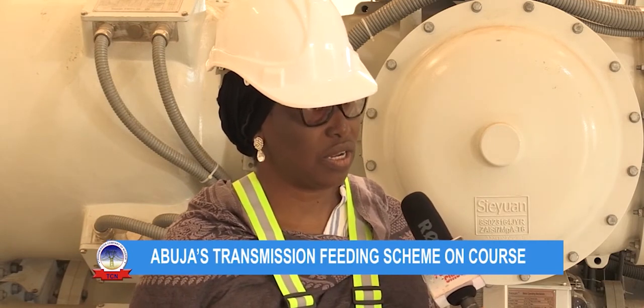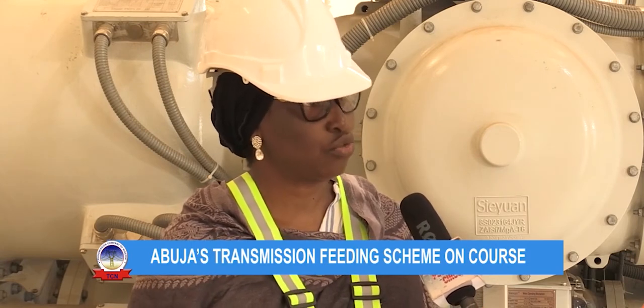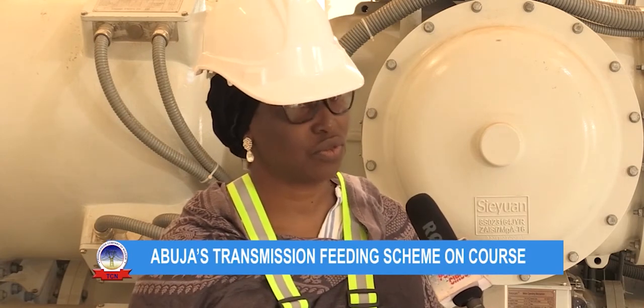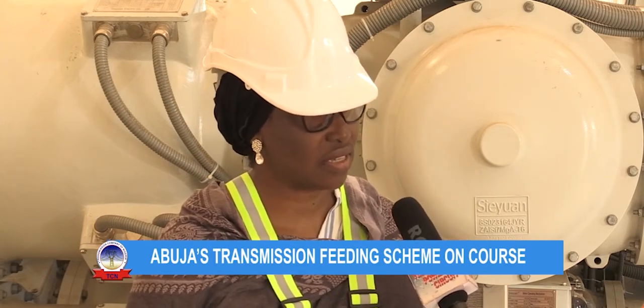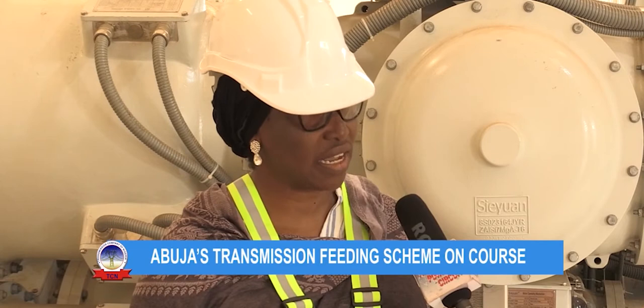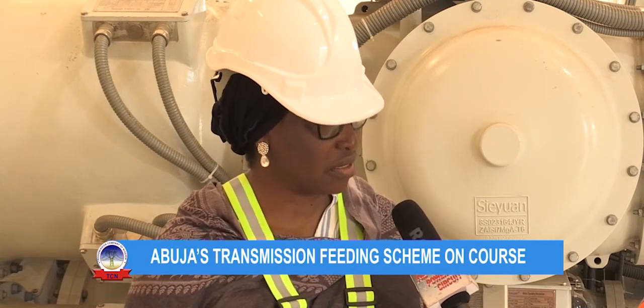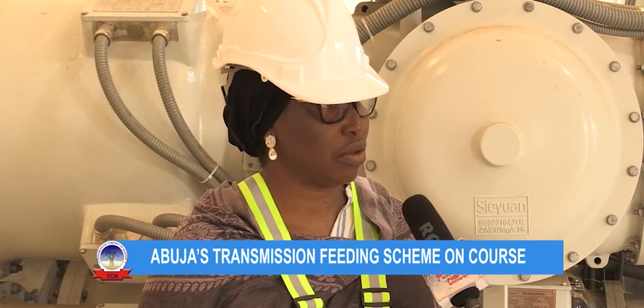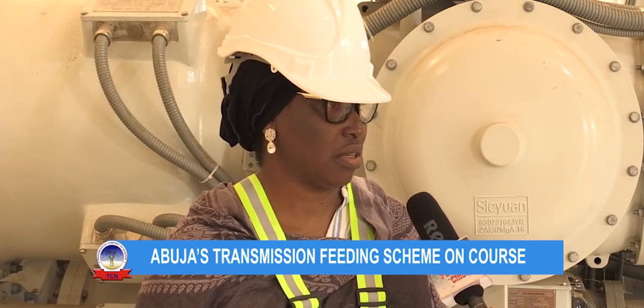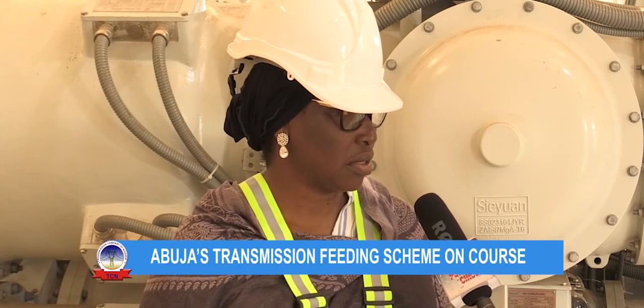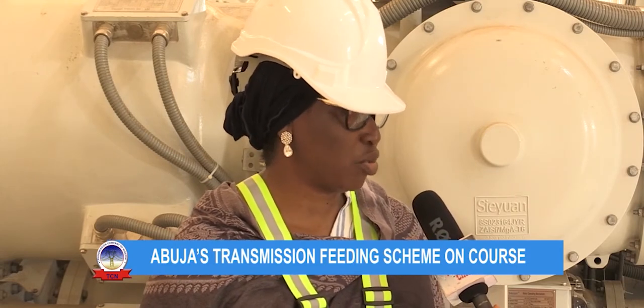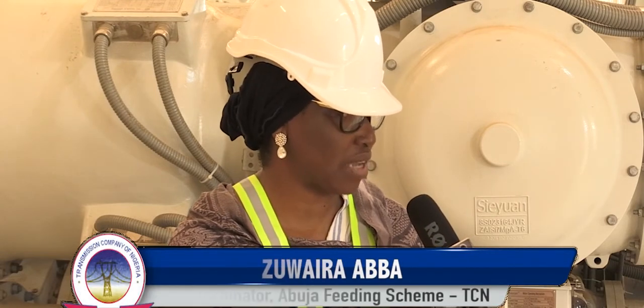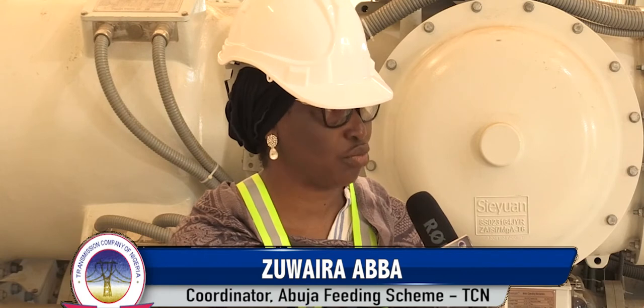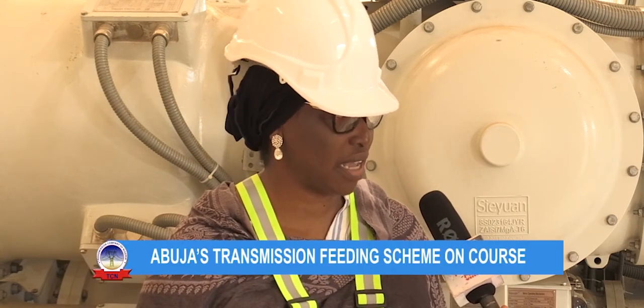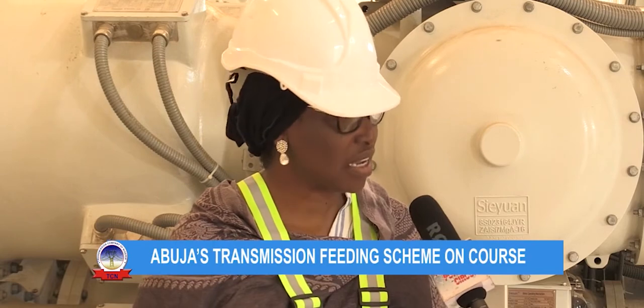So TCN management decided to break the line coming from Suleja to Katampe to build this GIS substation, which is meant to take less space and have almost free maintenance input at the end of the day. So this is practically the reason why the substation had to be a GIS, not the normal AIS substation, basically because of land constraint.